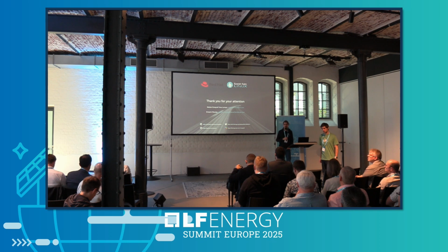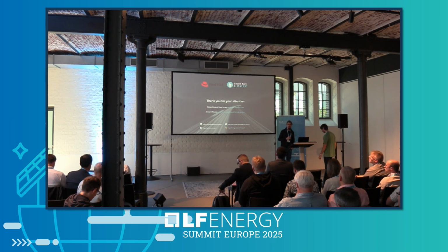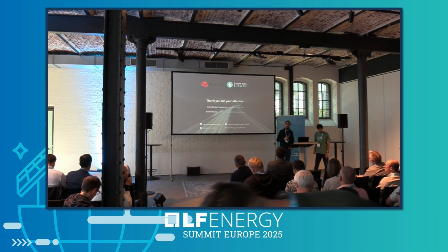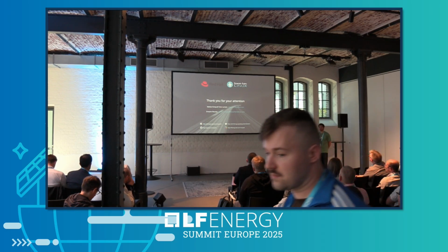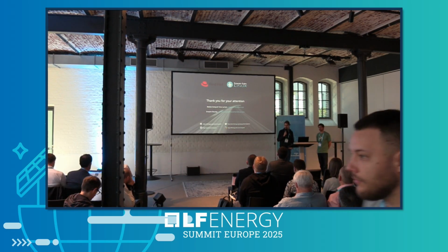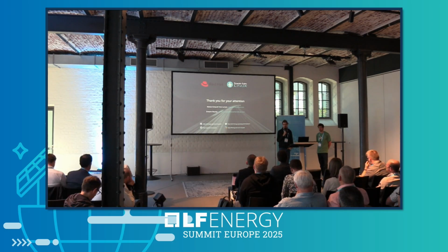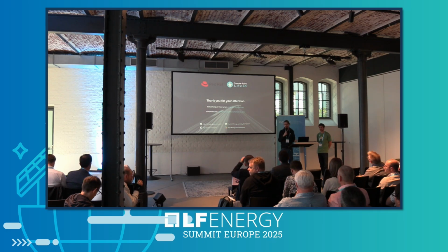Hello. If I, as a vendor, want to integrate a virtual IED in a virtual machine, how much effort do I have to put into it? It depends on the base you are already using for the virtual machines. Here we are using QEMU and libvirt files to deploy the virtual machines, and it was basically already the case, for example, for the ABB VM. So the challenge was just to have the correct configuration in SEAPATH, which doesn't take so many days of work. If you have a completely different technology, for example not QEMU virtual machines, it would be harder, of course, because you have to rebuild some things.